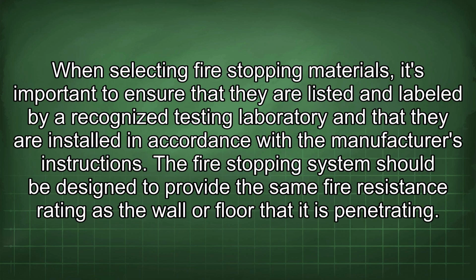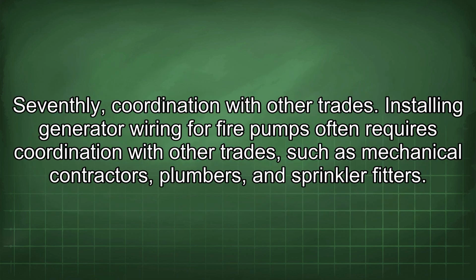When selecting fire-stopping materials, it's important to ensure that they are listed and labeled by a recognized testing laboratory and that they are installed in accordance with the manufacturer's instructions. The fire-stopping system should be designed to provide the same fire resistance rating as the wall or floor that it is penetrating. Seventhly, coordination with other trades.